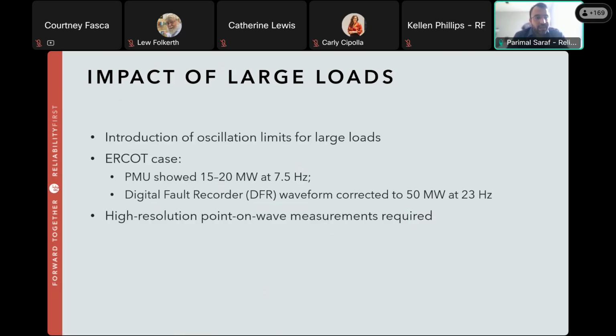So recently, there have been talks about setting oscillation limits for these large loads in terms of the magnitude of the megawatt swings, how much is allowed. ERCOT has proposed a limit on how much megawatt variation they will allow in order to control the risk of these loads inducing forced oscillations into the system.